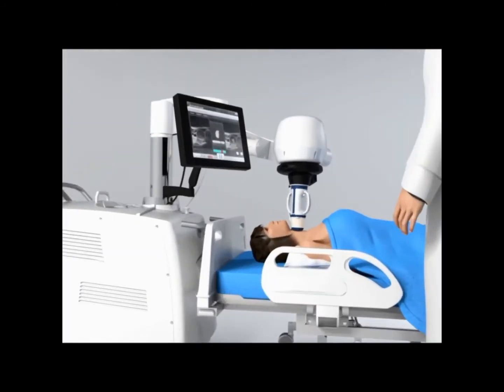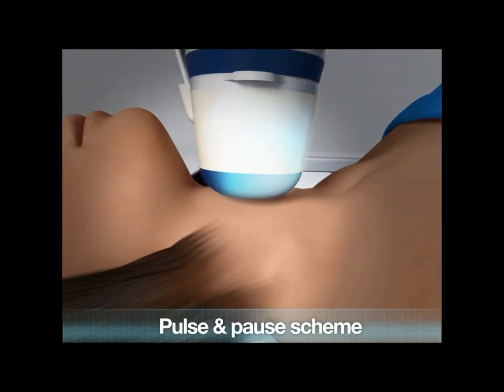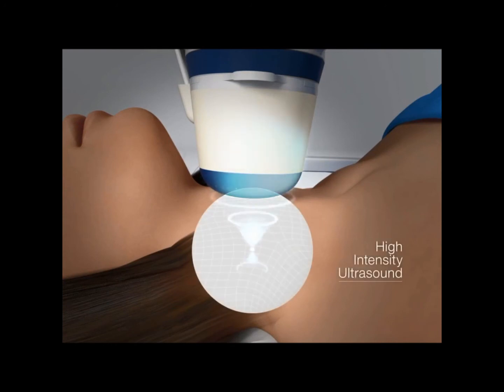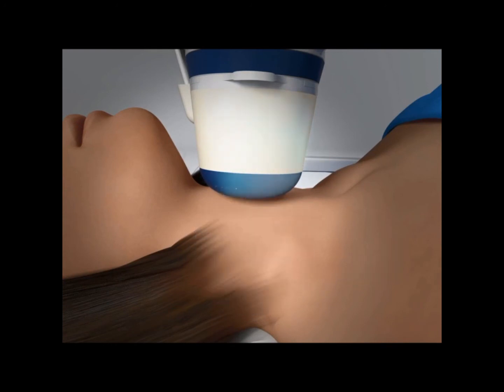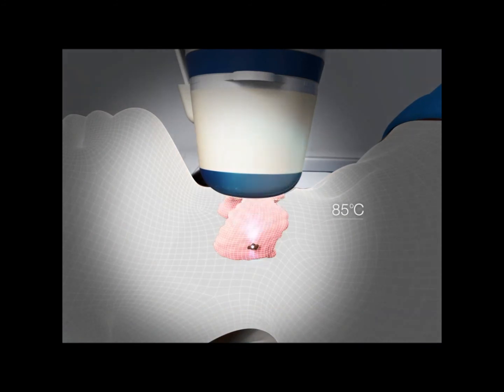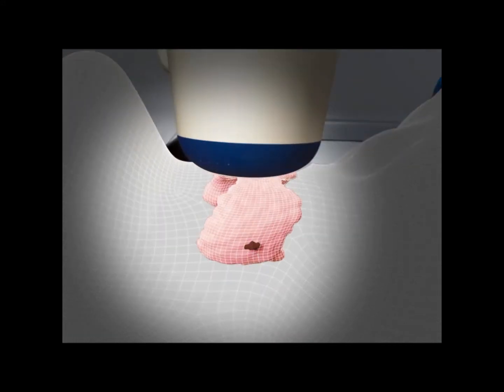The treatment consists of consecutive repeated pulses of HIFU over a pulse-and-pause scheme. HIFU technology focuses high-intensity ultrasound in order to deliver a large amount of sound energy on a confined space, inducing fast and intensive tissue heating of around 85 degrees centigrade. This beam will burn at its precise focal point, similar to sun rays through a magnifying glass.